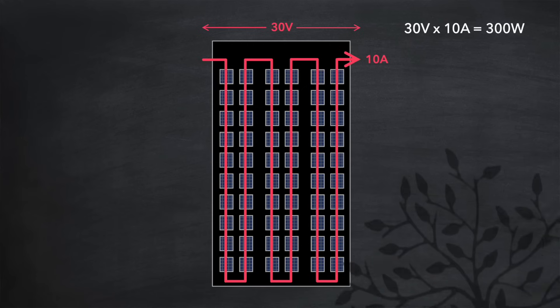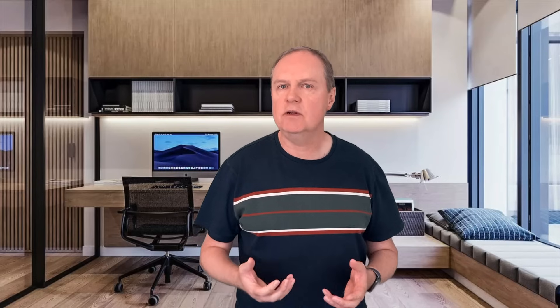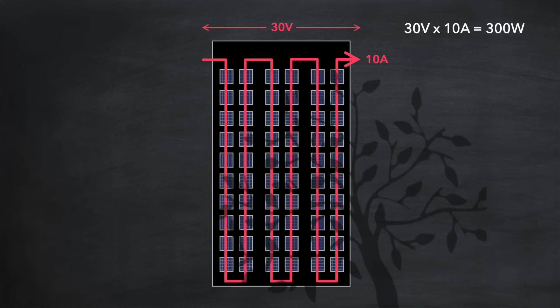Let's introduce some shading onto a few of the cells on this panel — let's say from a nearby tree. This type of shading is what we would call soft or diffuse shading, and it reduces the current flow through all of the cells experiencing that shading. Let's say the level of shading is around 10% across those affected cells. You might expect the impact on power output to be almost negligible — after all, there are only a few solar cells that are shaded, and even then they're still 90% operational. But here's the problem: because the current flow is reduced by 10% in those affected cells, the current flow through the entire panel is reduced by 10%, and therefore the total power output is reduced by 10% also, to 270 watts.